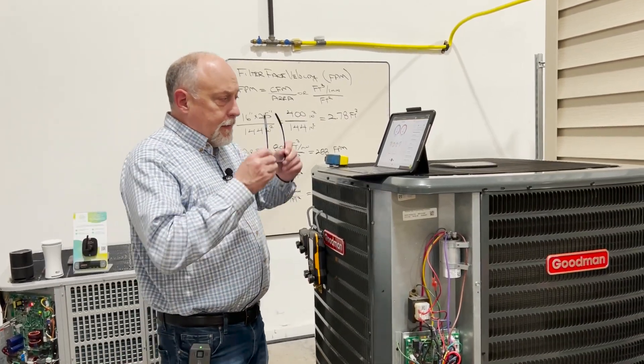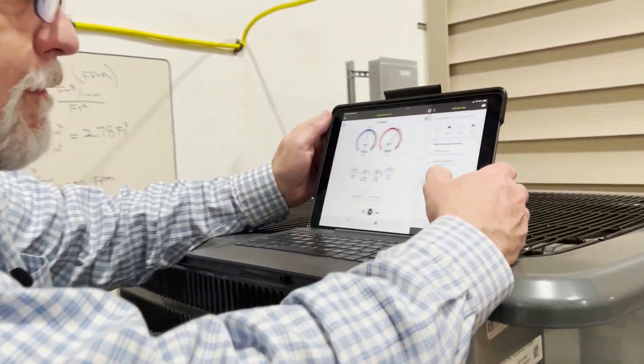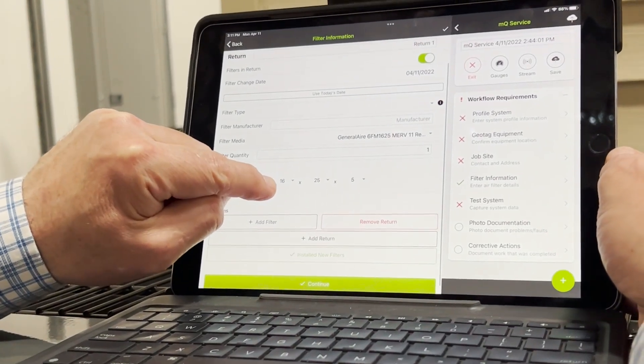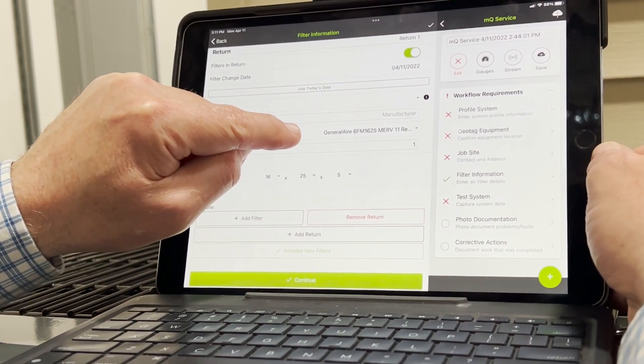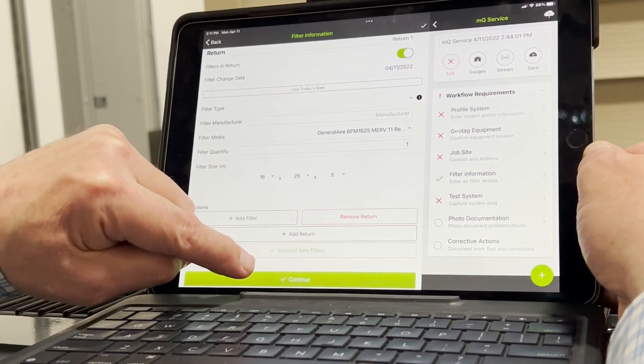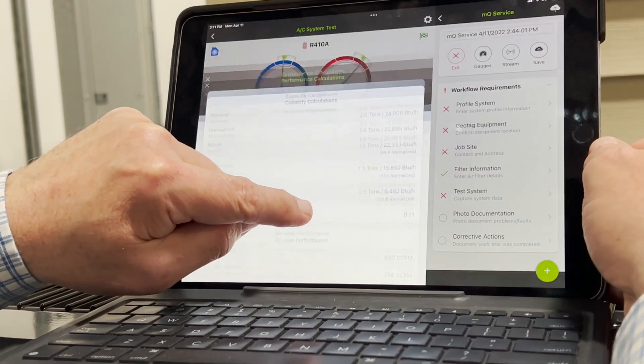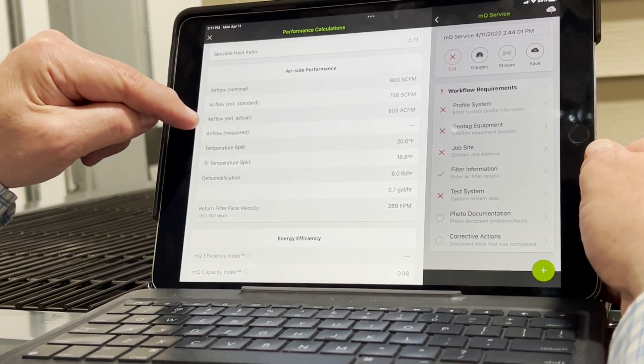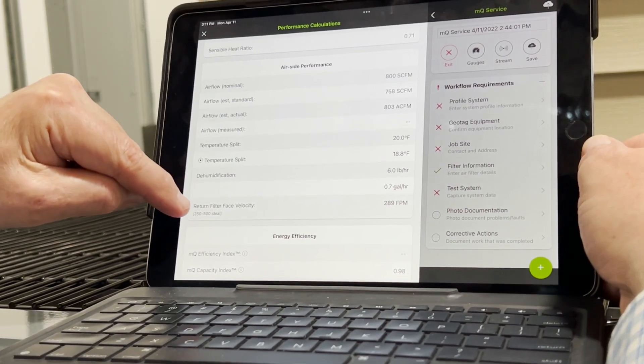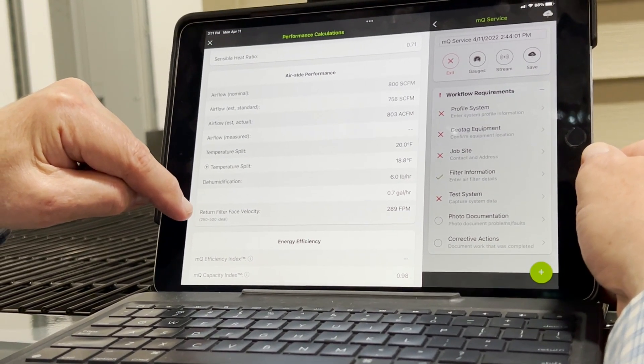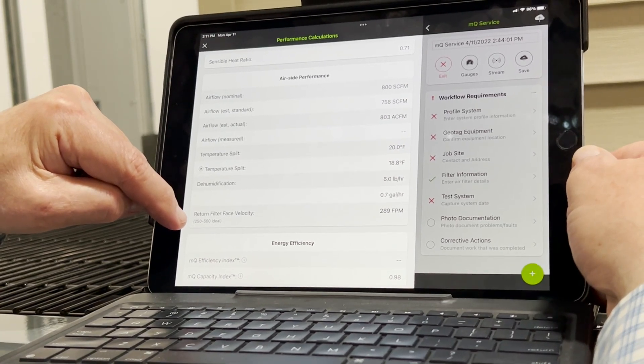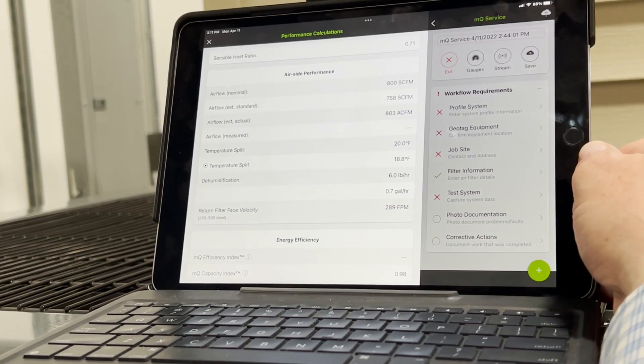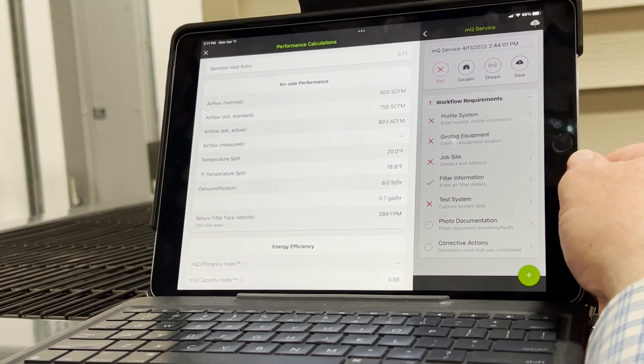So if you come over here and we'll take a look at MeasureQuick for just a minute. When you enter in filter information into MeasureQuick, a lot of times you're entering in — in this case I have a 16 by 25 filter, it's a GeneralAire, 16 by 25 MERV 11. I'll go ahead and hit continue on here. And then when we go to the performance section, you'll see that if we scroll down a little bit in our airside performance, we get obviously an estimated airflow calculation, but we also get down here a return air filter face velocity, and it's 250 to 500 feet per minute ideal. And in this case we're at 289 feet per minute. So that's the actual speed of the air going across the filter.